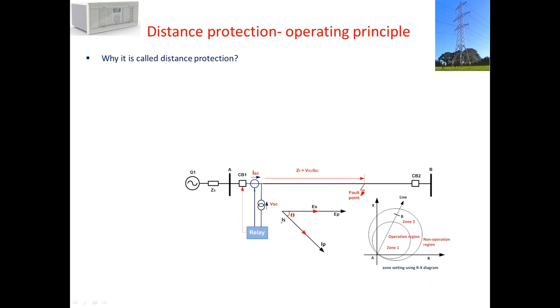To understand how the distance relay is configured or works, we need to understand why it is called distance protection in the first instance. One of the reasons is because the impedance of the transmission line is directly proportional to its length. When the line length increases, the impedance of the transmission line increases as well. That's the reason why it's called distance protection.